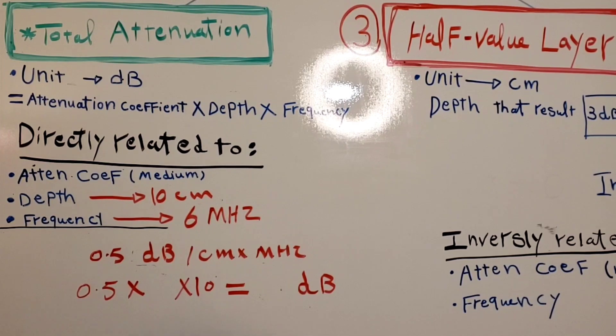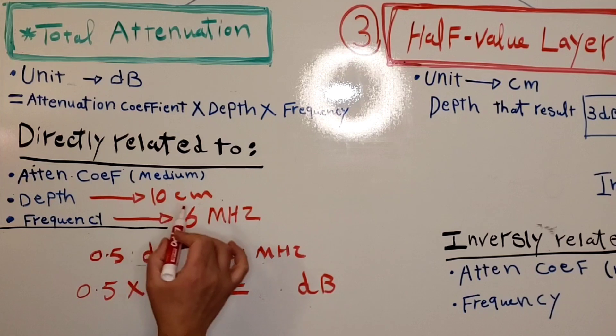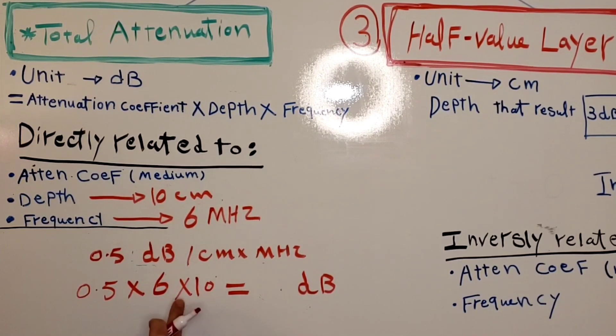Now changing the frequency to 6 megahertz with the same depth of 10 centimeters, and still assuming soft tissue with attenuation coefficient 0.5. Multiply 0.5 by 6 by 10 — 6 times 10 equals 60, and half of 60 is 30 decibels. So the total attenuation is 30 decibels.